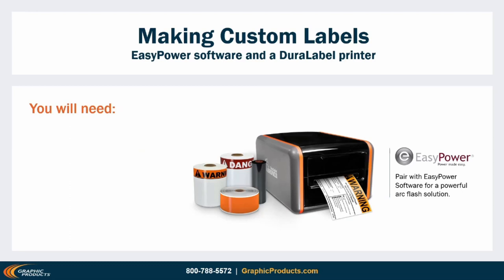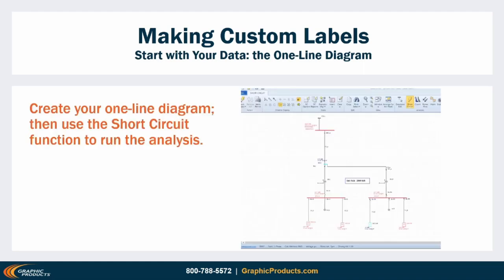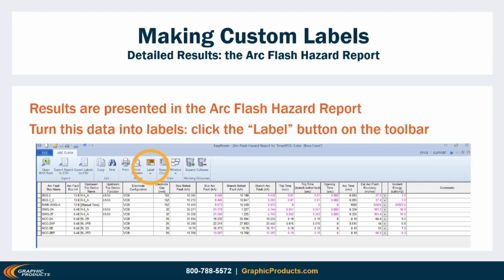Now that we've covered the context for arc flash labels, the requirements that apply to them, and how to make decisions about what goes on them, let's get practical. To make labels, you need your data and some way to arrange that data for printing, then a printer and label stock. I'll show you the steps to use EasyPower for the data and software parts, and a Duralabel printer and supplies for the physical end. In EasyPower, you'll create your one-line diagram, fill in the details for your facility, then use the short circuit function to have the program run its analysis and do all the math. When calculations are complete, you can view results in a table format as the program's arc flash hazard report.